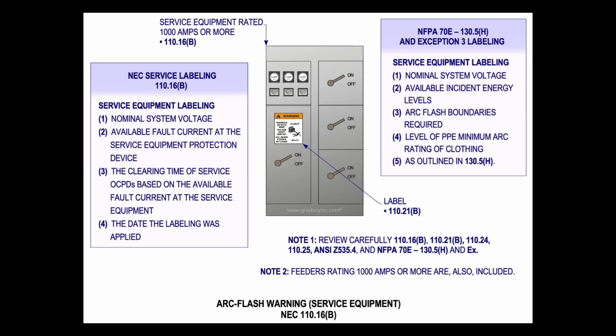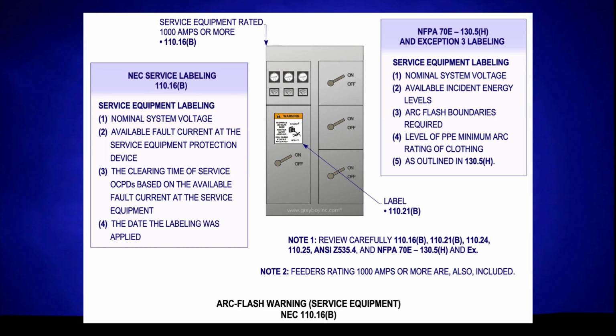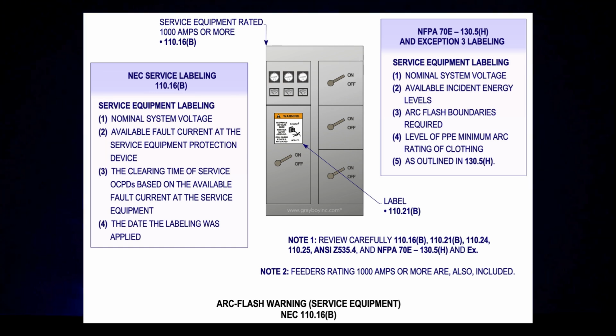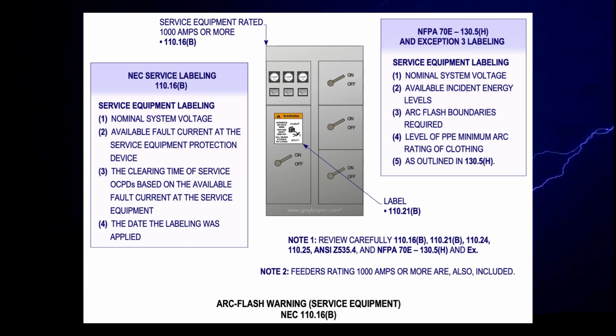The revision of 110.16(B) has incorporated the words "the arc flash label shall be in accordance with acceptable industry practice," which helps address the concepts of clearing times when arc energy reduction mode is applied, the values with and without arc energy values being applied, and arc flash incident energy level or clearing time in accordance with acceptable industry practice.